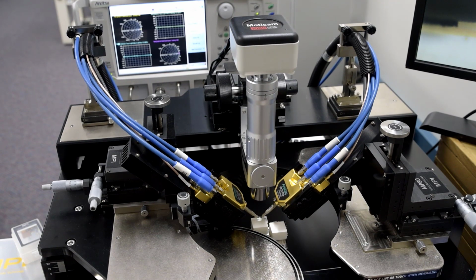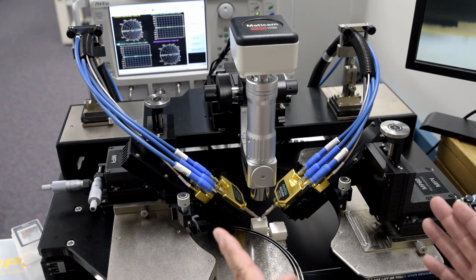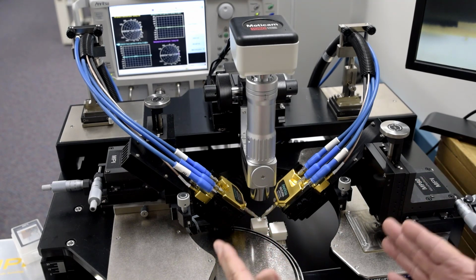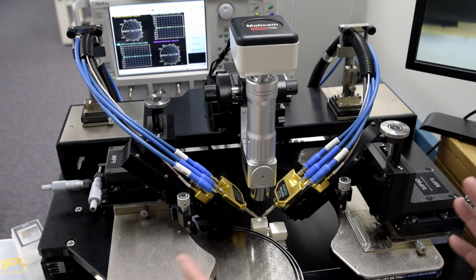So a very important aspect of mounting the Broadband VNA system to a probe station for probing applications is to mount the frequency extension modules directly to the probe. By doing that, you're going to maximize the raw directivity of the entire system. And it's raw directivity that has one of the most important aspects of determining the stability of calibration, especially for on-wafer types of measurements. And so you can review some of the other materials that we provide that discuss that in a little bit more detail.